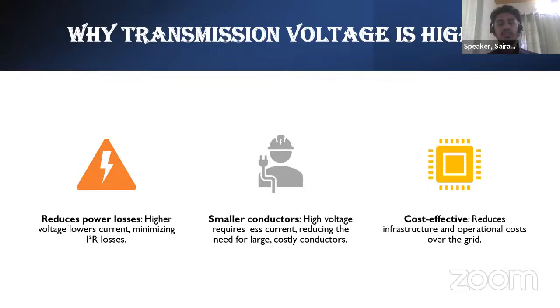Good. The answer that you have said was exactly right. The transmission voltage is always higher just to reduce the power losses. If you don't increase the transmission voltage, then the current in amps will be higher. If the current is higher, then I square R losses will be higher. If the losses in transmitting the power keep getting higher, it will be difficult to fix the economical cost and also for the generation. If they generate some 100 units, you have to get a good amount of quality power at the user end. If more energy is wasted in I square R loss, it won't be feasible for generating and transmitting. That's why they use higher voltage in transmission.